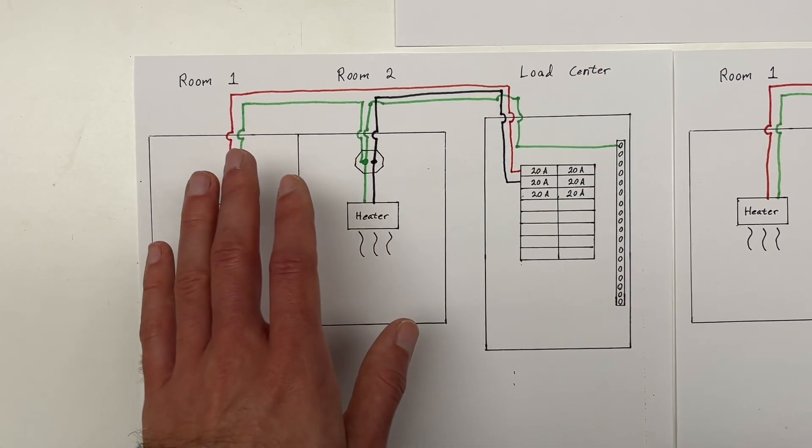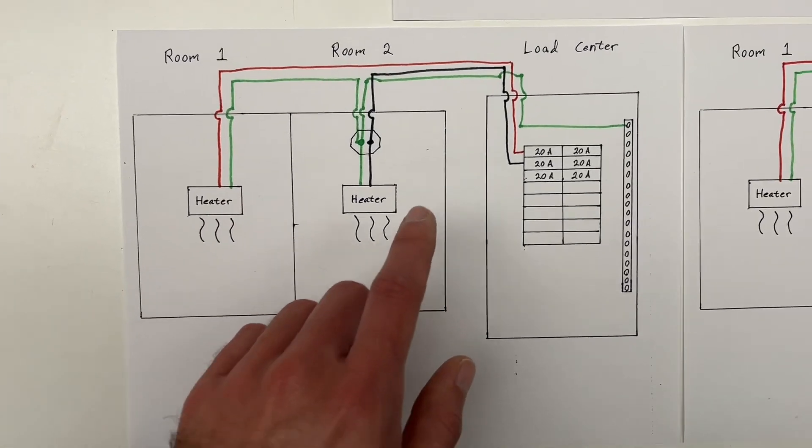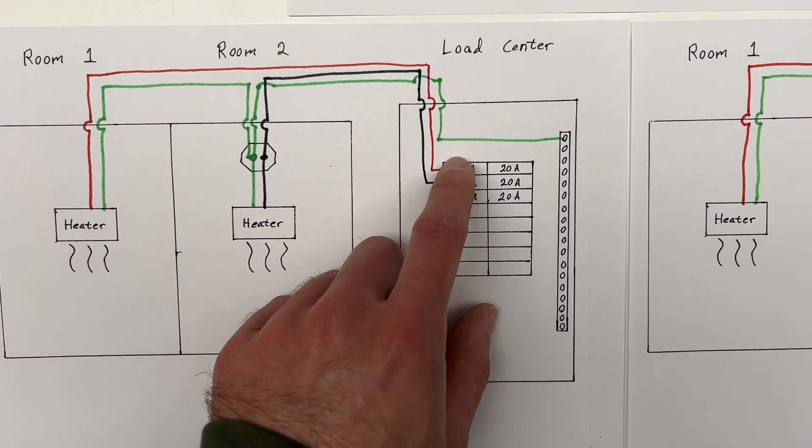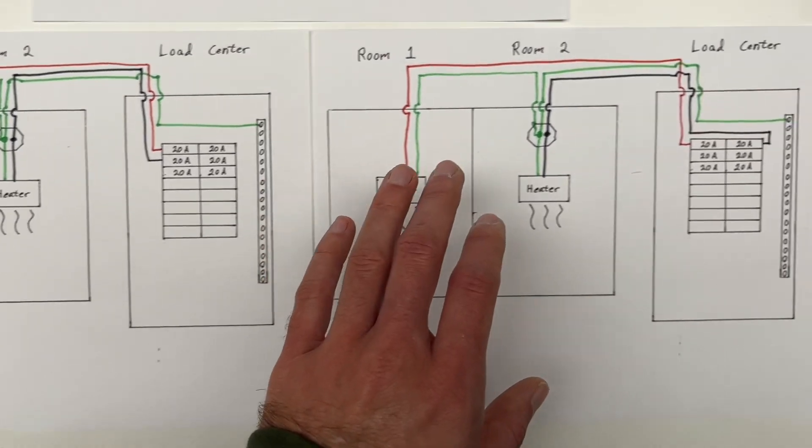This is okay, but you have to do it safely, which means that you have to run your red and black wires to vertically adjacent breakers. What happens if you don't do that?